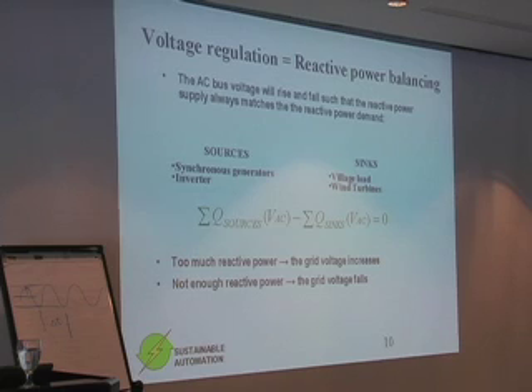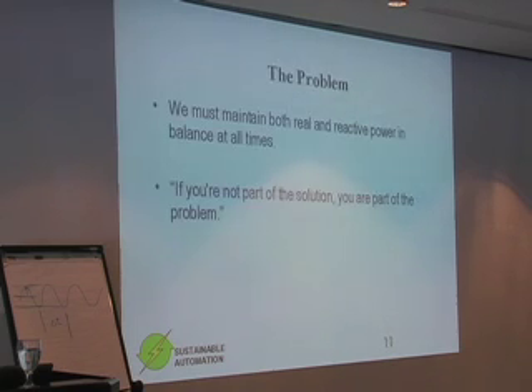Similarly, the problem of voltage regulation is a question of balancing reactive power. There's a subtle difference here: reactive power can't be stored. So it turns out that whatever you do, the supply of reactive power will necessarily equal the dissipation of reactive power at all times. The problem is that you need to provide the reactive power which will hold the voltage at a certain level. If there's too little reactive power compared to what's demanded by the system, the voltage will sag. Similarly, if there's too much, the voltage will rise. So that's the problem. At all times, we must maintain a balance of real and reactive power.